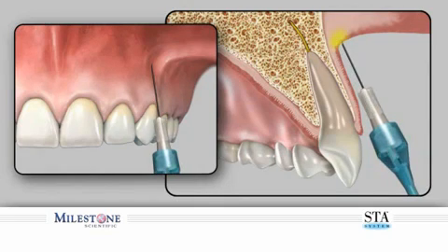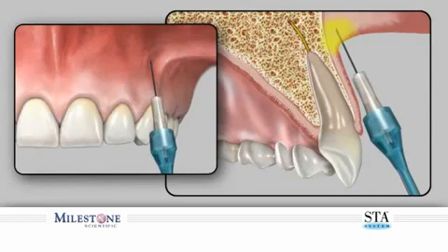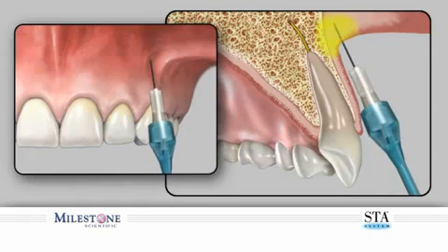Hold the handpiece very delicately and insert the needle using a slight back and forth rotation. Continue with a slow insertion, which may take several seconds to reach the target. If an aspiration test is required for the specific infiltration, perform an aspiration by depressing and releasing the foot control pedal. If the aspiration is negative, you can continue the infiltration injection and administration of anesthetic solution to the area. If aspiration is positive, reposition the needle and perform another aspiration by depressing and releasing the foot control pedal.